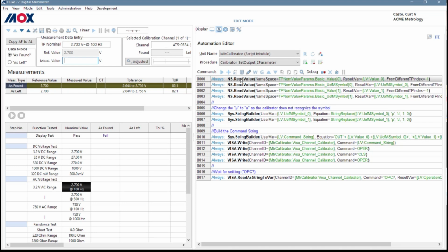What do you mean by hard coding? Well, with a MET/CAL procedure, you're telling it these are the test points you're going to check. This is going off of your exact data sheet that you already have, correct? Correct. Yeah, it's actually reading the values from the test point. So it's totally different. That's a game changer. Yeah.